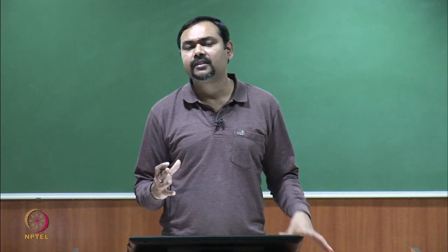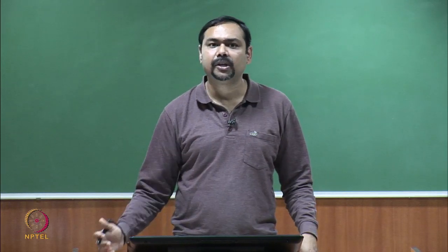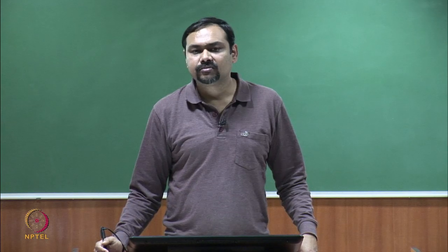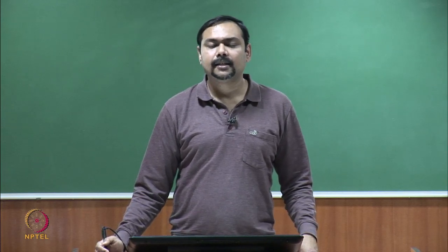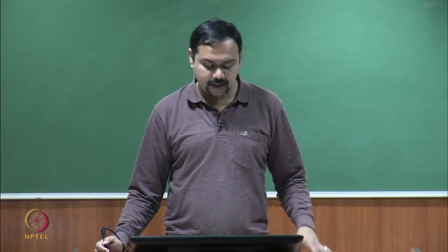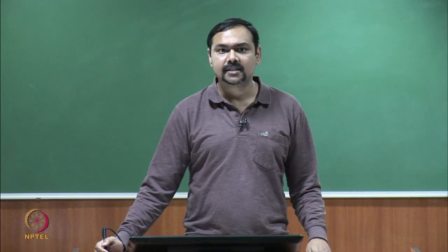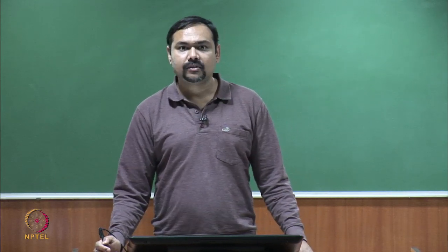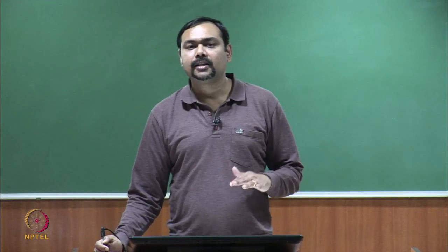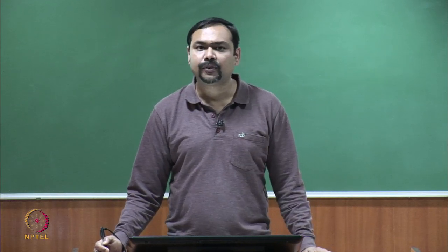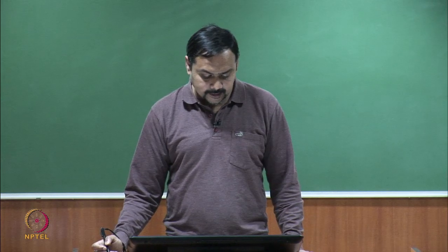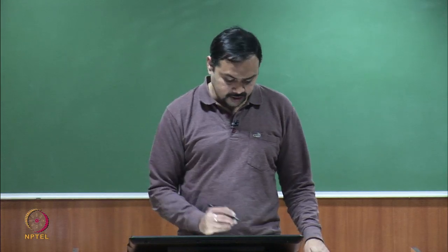This is not a standard transformer, and several tests have to be performed on it to get accurate figures: how much is the input current cancellation, how much are the forces on the transformer during short circuit. There are many tests which have to be performed. So, it is an elaborate arrangement.